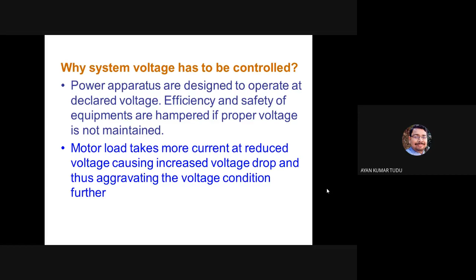A higher than nominal voltage also leads to overcurrents. How? When high voltage is applied to a motor, it tends to push the magnetic portion of the motor into the saturation zone. It will cause the motor to draw excessive current in an effort to magnetize the iron beyond the point to which it can be easily magnetized. Because of that, there can be heating and burning of the motor. Understood? So why the system voltage has to be kept constant, I think that question's answer we can also find out. Understood till now?